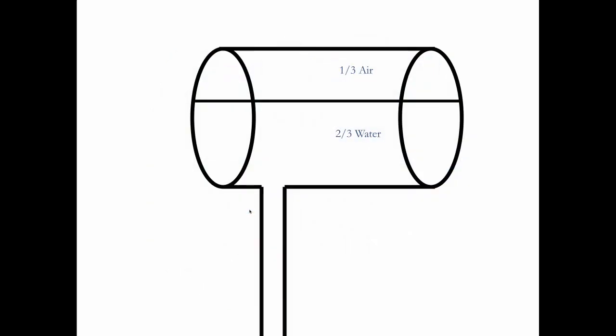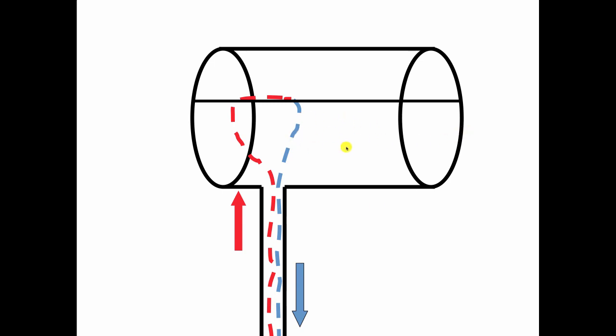So we use it all the time in heating. This is a compression tank — not with a diaphragm. It's the old school compression tank. We fill it two-thirds with water, one-third with air — always put the air on top. Now, if this is attached to a hot pipe in the system, the heated water in the system is going to rise up by gravity and bring the cooler water down. Henry's Law says since we're not pumping water through here with the circulator — and the circulator cannot add or remove water to the compression tank — the water in the tank is going to be cooler than the water in the system. So when you get this kind of gravity circulation naturally happening, the air in the cushion gets absorbed into the tank water because of Henry's Law.